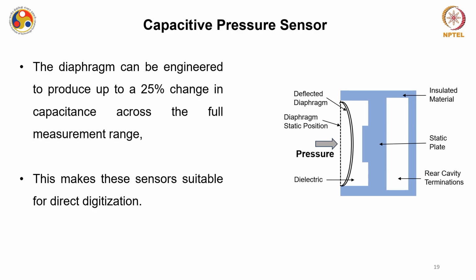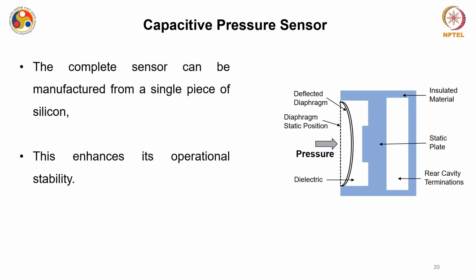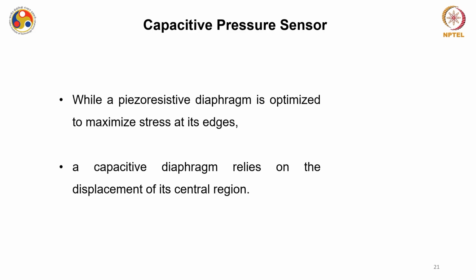The diaphragm can be engineered to produce up to a 25% change in capacitance across the full measurement range. With such a large range, you don't need external measures to digitize the process, since the changes are already large — making this kind of sensor suitable for direct digitization. The complete sensor, as mentioned, can be manufactured from a single piece of silicon, which has multiple advantages, along with certain demerits that we will discuss.